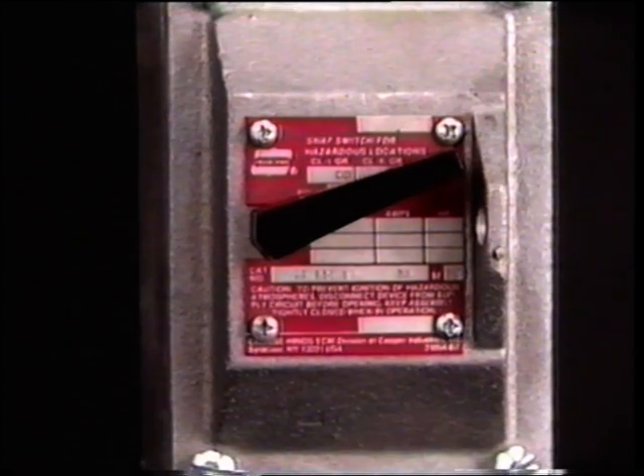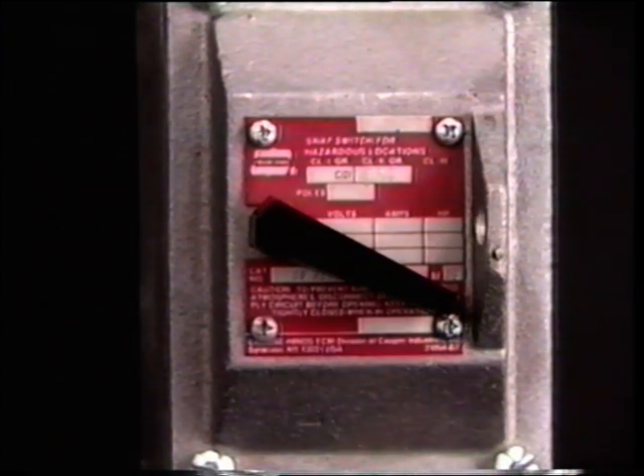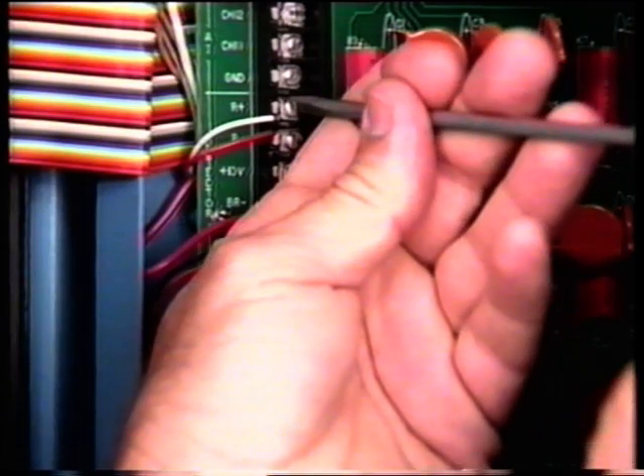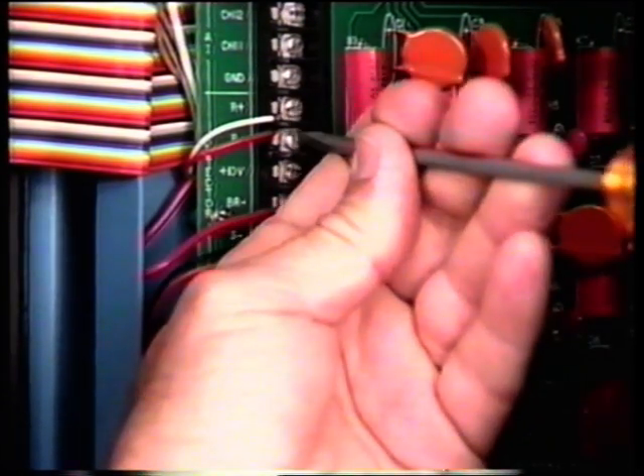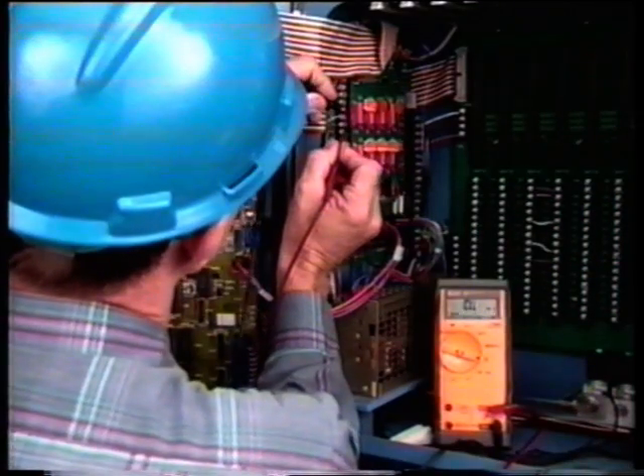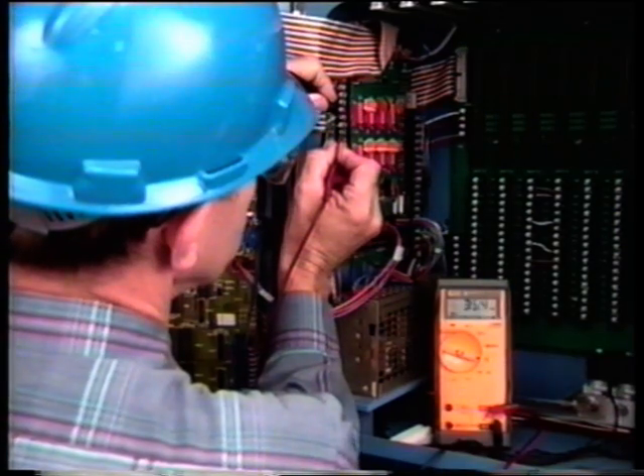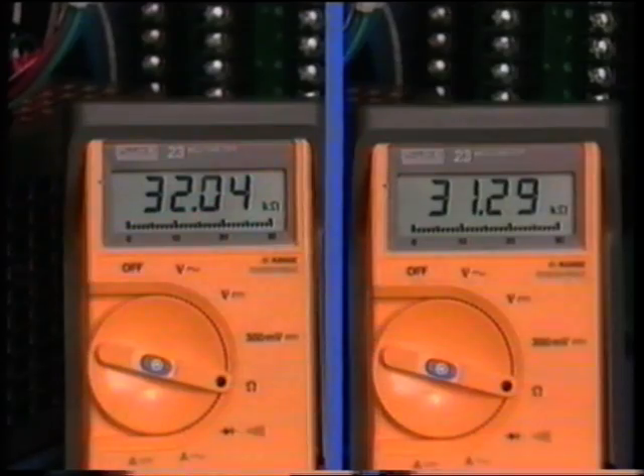Next, verify thermistor resistance. To do this, turn off the power to the analyzer. Disconnect the wires of each thermistor at the terminal strip. Use a multimeter to measure the resistance of each thermistor and check for shorts to ground. The measurement or sense thermistor resistance and the reference thermistor resistance should be within 10% of each other. The resistance to ground should be greater than 1 megohm.